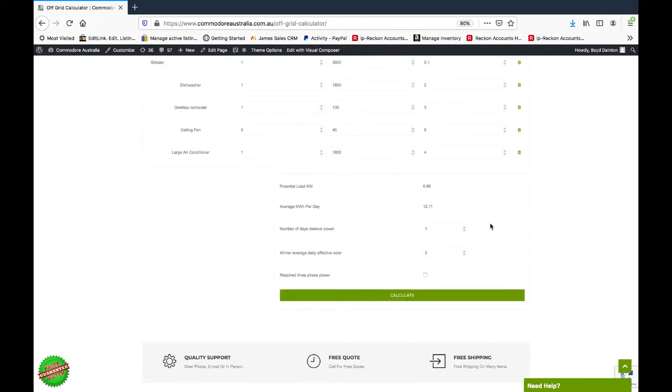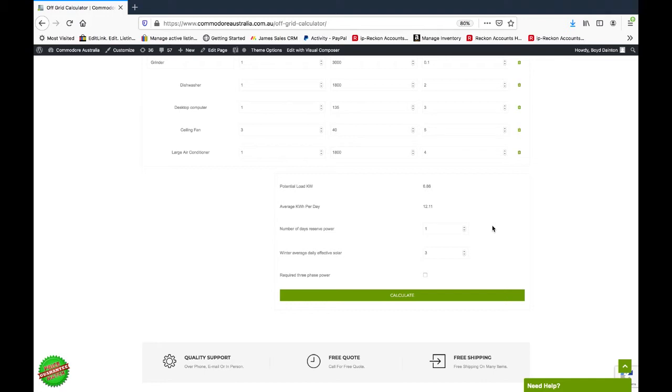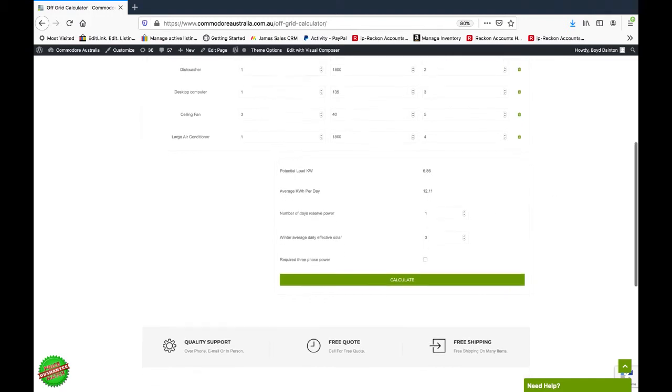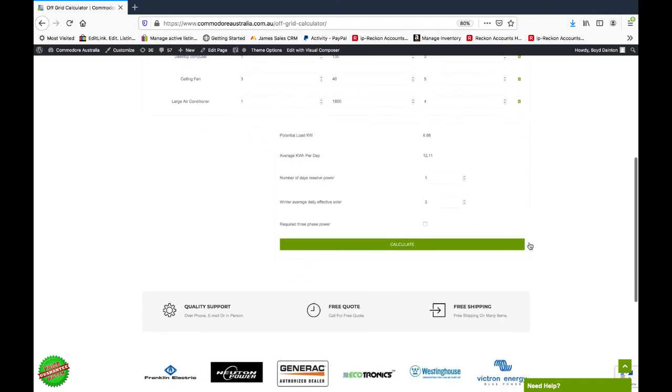Moving down, we've got number of days reserve power. We've just set that as a standard as one. That's basically how many days of battery backup you want. You want at least one day of battery backup if you've got a generator. If you're not going to have a generator on your system, you'd want at least two days of reserve power.